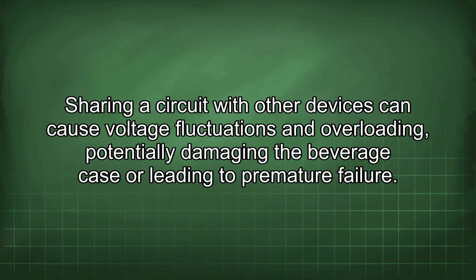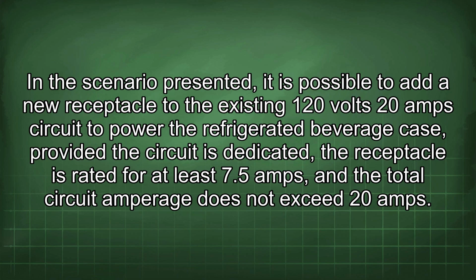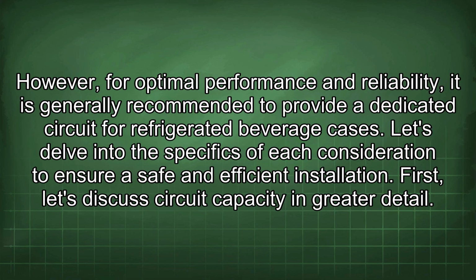Sharing a circuit with other devices can cause voltage fluctuations and overloading, potentially damaging the beverage case or leading to premature failure. In the scenario presented, it is possible to add a new receptacle to the existing 120 volts 20 amp circuit to power the refrigerated beverage case, provided the circuit is dedicated, the receptacle is rated for at least 7.5 amps, and the total circuit amperage does not exceed 20 amps. However, for optimal performance and reliability, it is generally recommended to provide a dedicated circuit for refrigerated beverage cases. Let's delve into the specifics of each consideration to ensure a safe and efficient installation.